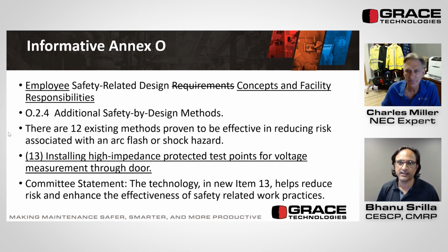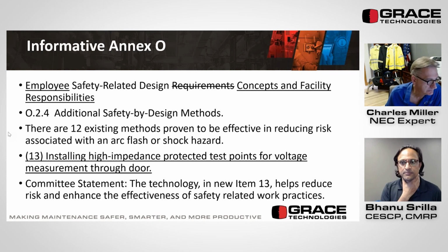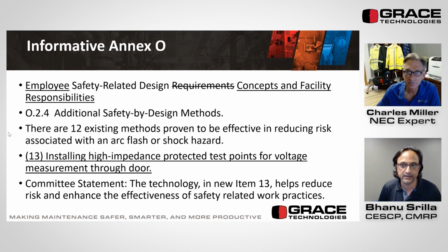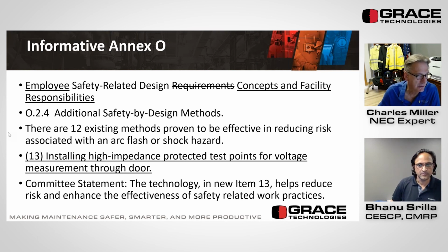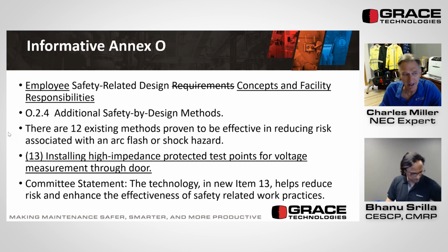Yeah, I definitely think, Charlie, that point is going to get a lot of public comments, because from the perspective of the operator, the available fault current rating isn't in the hands of the qualified electrical worker - that's beyond their control. And someone made a comment here that's absolutely true: if the utility changes the transformer, you have to update your arc flash study per NFPA 70E. Absolutely, yeah, that is an absolutely true statement. I don't know if that's always done, but that is correct.